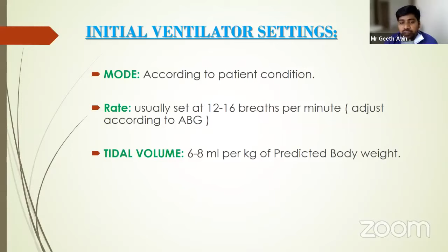Then the rate. Usually we set around 12 to 16 breaths per minute. As per ABG, when there is hypercapnia or acidosis, we will be adjusting the rate. Tidal volume has to be initiated at 6 to 8 ml per kg of predicted body weight. The inspiration to expiration ratio is usually 1:2 or 1:3. It can be prolonged in COPD cases. PEEP is around 5 to 10 centimeters, and FiO2 is initially delivered at 100%. As per the PF ratio calculated in ABG, you can adjust or decrease it as the ABG demands.